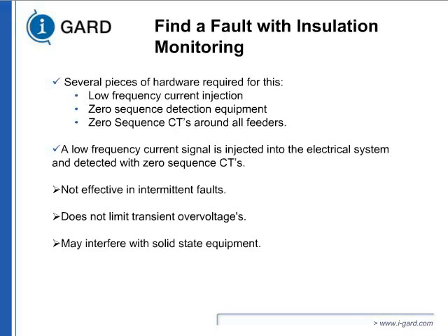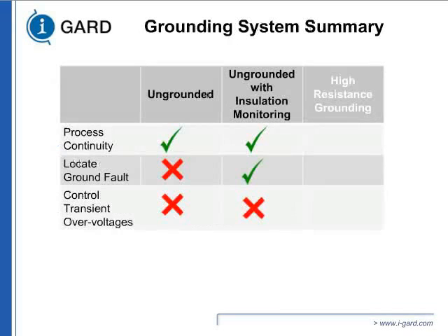So now you see we're building up. Ungrounded gave process continuity. So does ungrounded insulation monitoring. Ungrounded system could not locate the ground fault. Ungrounded insulation monitoring gave us a capability that we can locate which system might be affected based on insulation. But still, it does not control the transient overvoltage. So insulation failure is not prevented, it is just predicted when it can happen. So you still have to shut the system down.